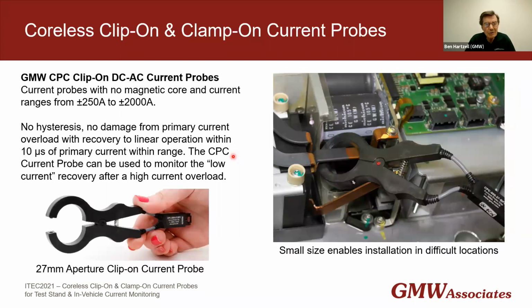So the first one is what we call a clip-on current probe. It has a 27 millimeter aperture. So the sort of thing is something like this. So the aperture here is 27 millimeters. You can see that it's very small compared to the aperture, both in the in-plane version, but also perpendicular to the current. It's very slim, so you don't need very much axial length to insert the probe. And this shows a clip used on a bus bar in a charger, and it is just clipped around and the leads. It's an analog output, so that goes to some sort of analog processing system.